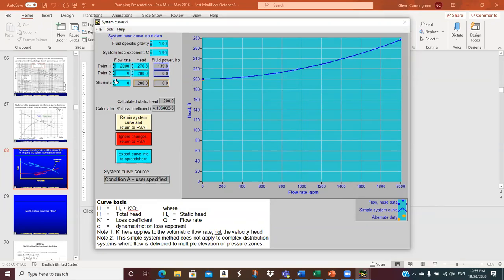Well, one point is usually the zero flow point. Because at zero flow, the only head that you need is the static head in the system. So let's say that you had to pump from this tank to one up on the hill, and the difference in elevation from the free surface here to the free surface here is 200 feet. So at zero flow, you still require 200 feet in order to get water from this tank to that tank. And it has nothing to do with friction. It has to do with how tall the hill is. Okay, so that's what we call static head.